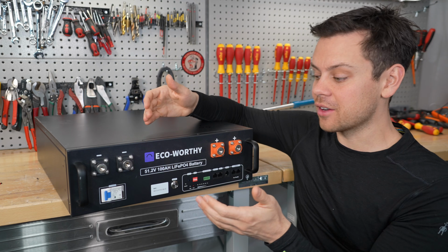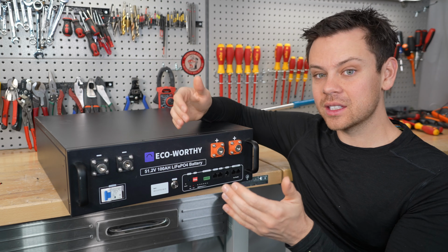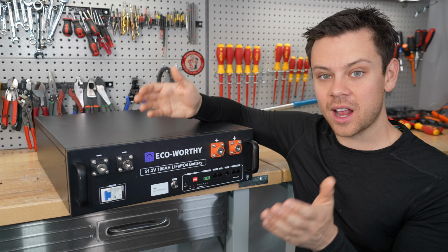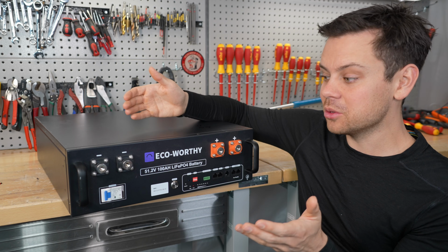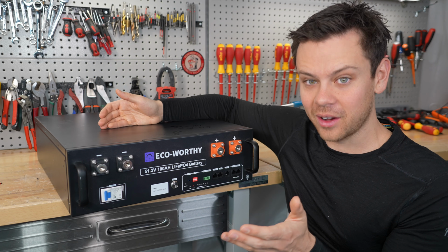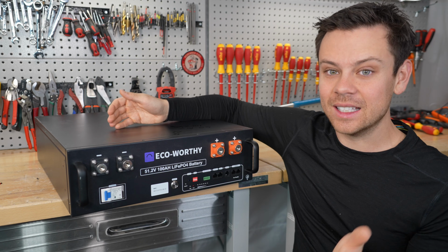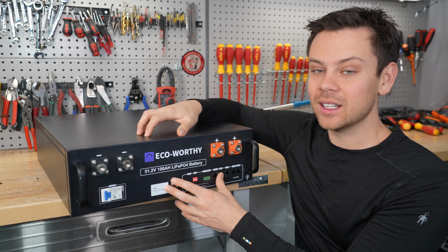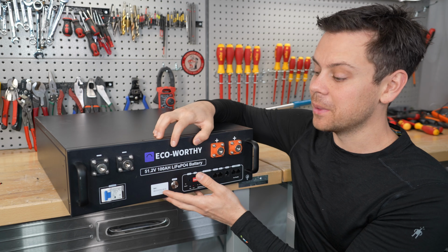With that method of measurement, and resetting after every cycle, you're gonna get around the same results every time, around 100 amp hours. Sometimes we'll get all the way up to 104, sometimes we'll get 99, but there is more capacity we can't access because the BMS is limiting it.